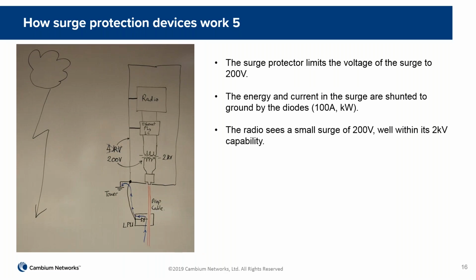So in the case then where we have fitted an LPU, our 4 kilovolt surge again travels up the drop cable, and this time is diverted by the LPU and flows to ground. And the voltage that is seen and passed across to the radio is of the order of 100 to 200 volts. And as I've mentioned before, the radio is quite capable of withstanding that voltage. So our system is saved, our system is protected by the addition of this LPU, surge protection device, ahead of it.